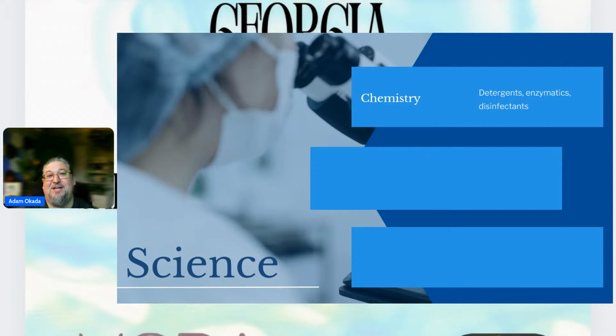Disinfectants are only effective if you have wet contact time. One common disinfectant I see quite a bit is alcohol. What people do is they take their instrumentation, spray it with alcohol, and then pass it over to the clean side. The problem is that you need 5 minutes of wet contact time with alcohol for it to be an effective disinfectant. I don't know if you've worked with alcohol before, but it dries very quickly. That thing would be dry in maybe 20 seconds. So that's not the wet contact time. We're not actually killing the microorganisms we think we are.